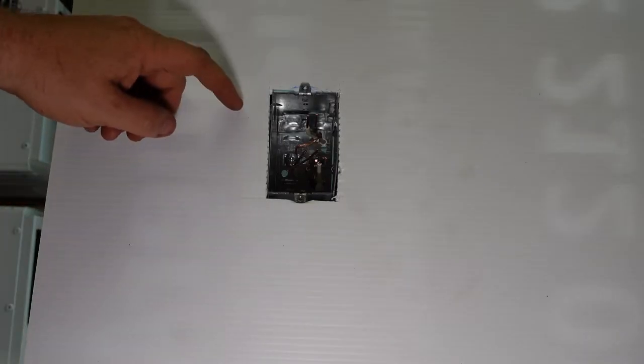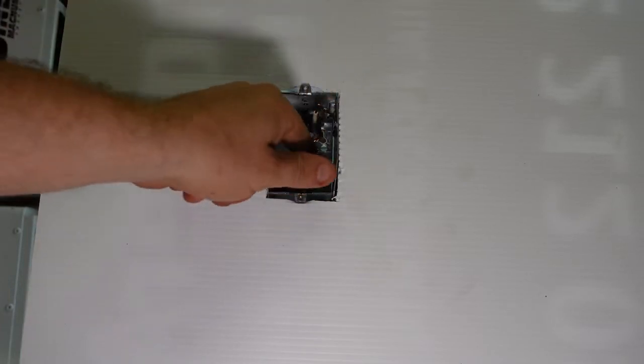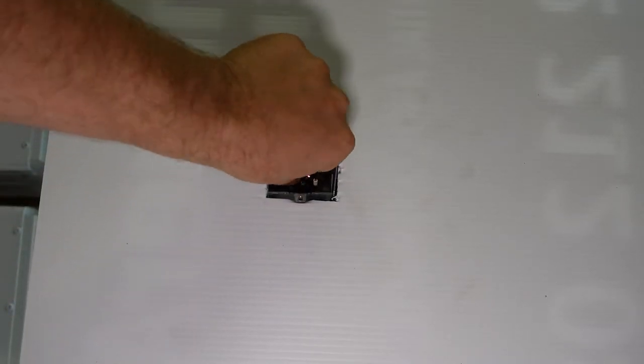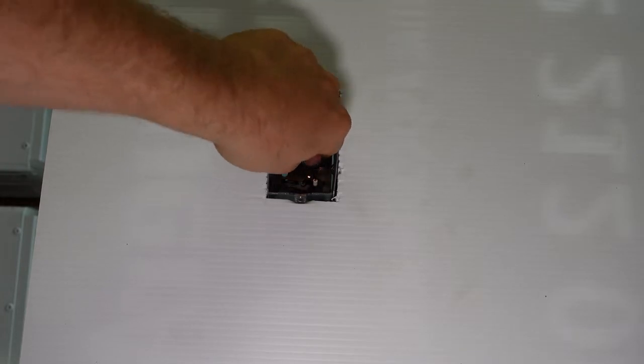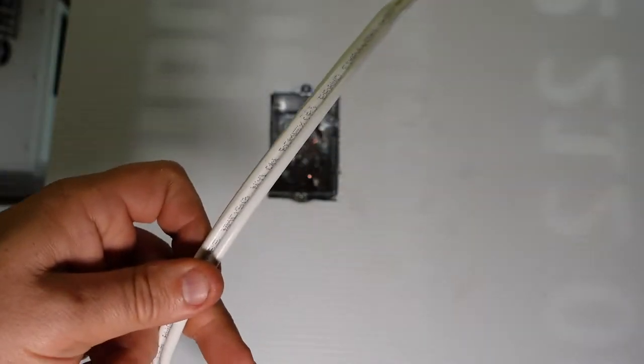Now from a front angle, you can see inside the box that the ground wires are actually too short. So the first thing we need to do is to make these ground wires longer. So what we're going to do is strip a piece of 14-2 wire. I'll go ahead and strip that. And this will expose the individual ground and the individual black and the individual white so that we can work with it.